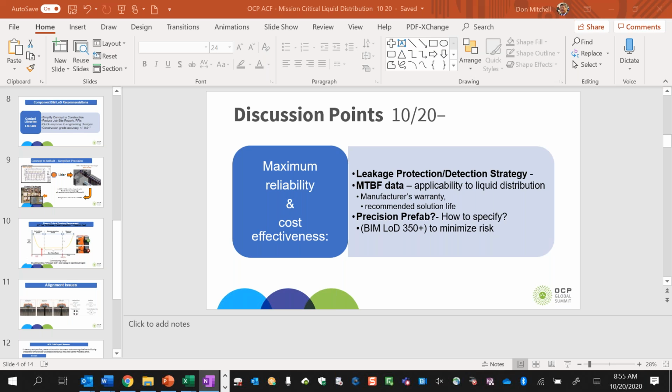But the bigger gap was the actual installation, in that we didn't have turbulence or any erosion going on, or collection of, well, we didn't have chemical issues because we had very clean water. But the valve is an issue. You could specify that, but to the comments on this call already, the mean time to failure in the piping systems is really not manageable.